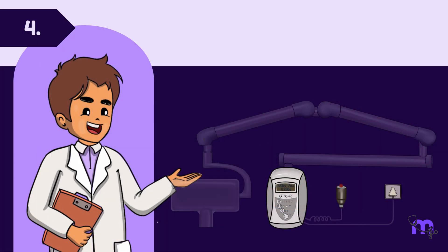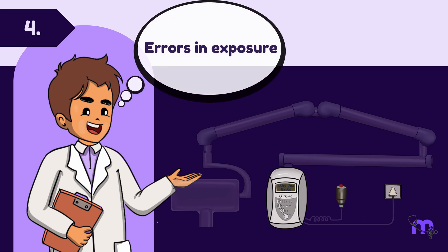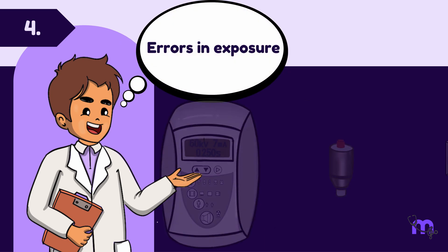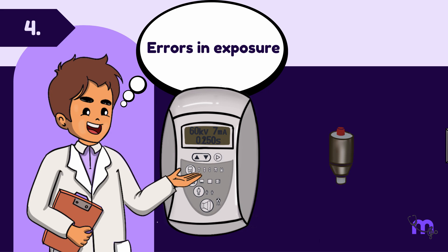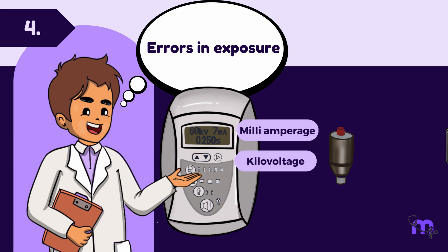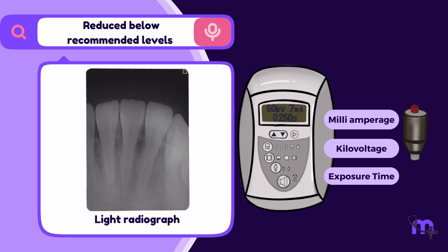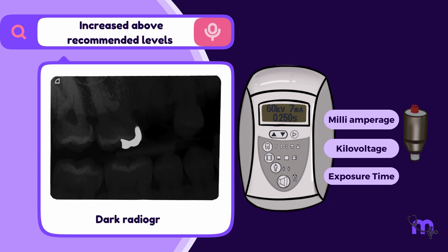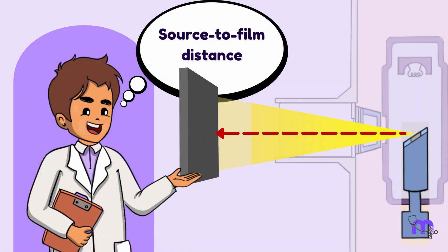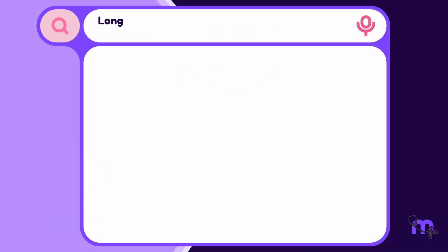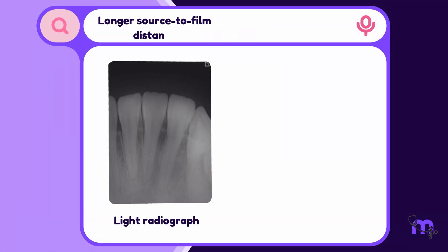After correctly positioning the PID, the patient is exposed. Exposure settings significantly impact the final radiograph. These settings include mA, kV peak, and exposure time. If these factors are all reduced below recommended levels, a light radiograph is produced. Conversely, increasing all three factors results in a darker image. The source-to-film distance also affects image density — a longer distance results in a lighter image, while a shorter distance produces a darker image.